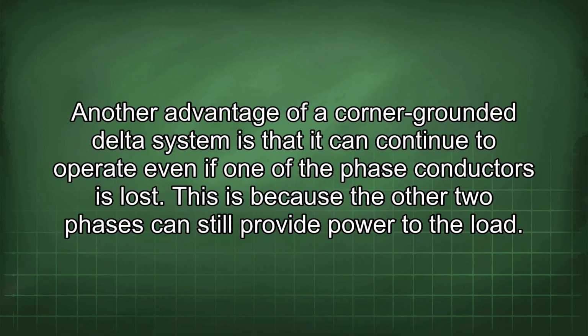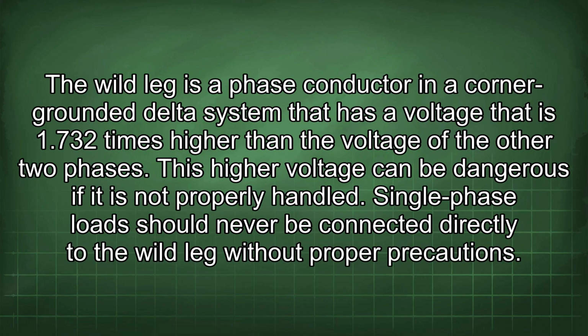Another advantage of a corner-grounded delta system is that it can continue to operate even if one of the phase conductors is lost. This is because the other two phases can still provide power to the load. The wild leg is a phase conductor in a corner-grounded delta system that has a voltage that is 1.732 times higher than the voltage of the other two phases.